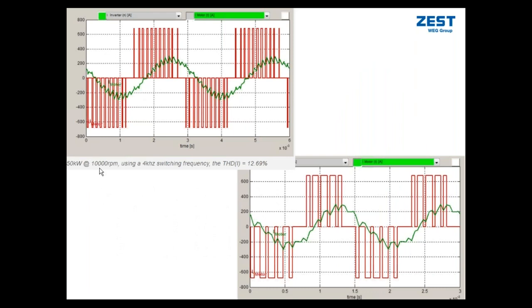This is just another view of the same thing. In the top example, we have an output power from the VSD of 50 kilowatts at 10,000 RPM using a 4 kilohertz switching frequency. We can see that the THDI is 12.69%. In the second case, all we are doing is keeping the switching frequency the same at 4 kilohertz, but we are doubling the speed, hence we are doubling the output power. But in this case, because we've increased the voltage and the modulation index, we have now seen an increase in the total harmonic distortion of current. And that's just to set some of the basic principles, which we'll get into in a little bit more detail later.